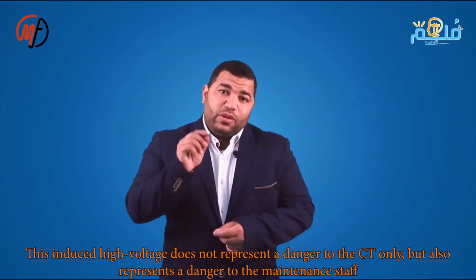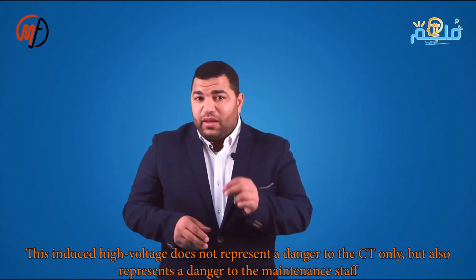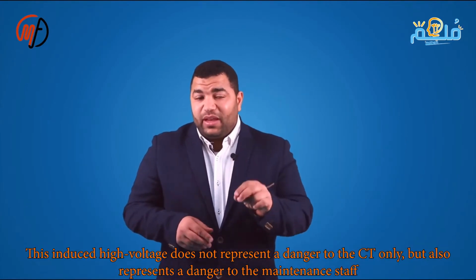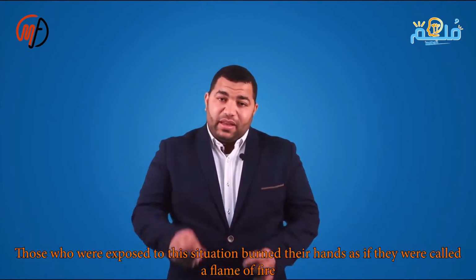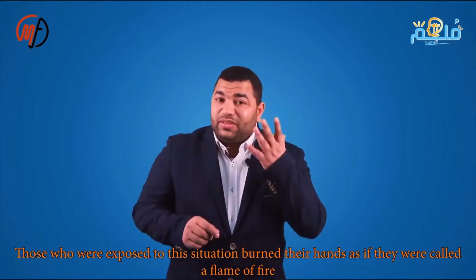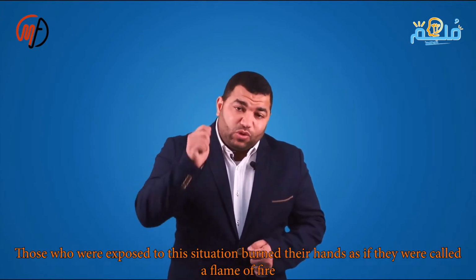This high voltage poses a danger to the transformer and the people. Those who experienced this had their hands burned like holding a flame. If you must remove the relay when the line is live or in error, short the CT secondary terminals before relay removal.